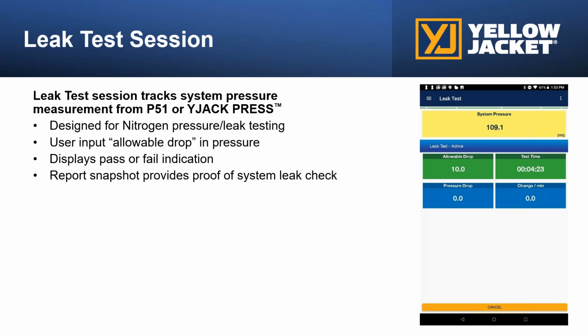You can do a leak test. So this is really important. When I mentioned how our app and our digital manifold can tell a contractor if they installed a mini split or VRF system correctly, basically, how a contractor would do that is, depending on the mini split or VRF system that they're installing, different manufacturers specify different, call it allowable change, different pressure drop during this pressure hold test. And typically a pressure hold test for a mini split is a 1 or 2 hour test. And then a pressure hold test for a VRF system could be up to 24 hours.